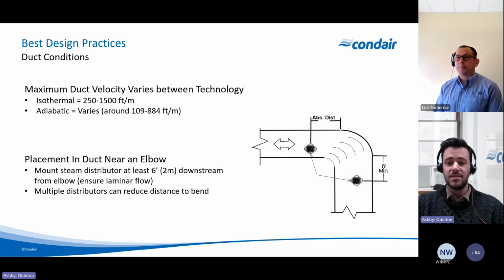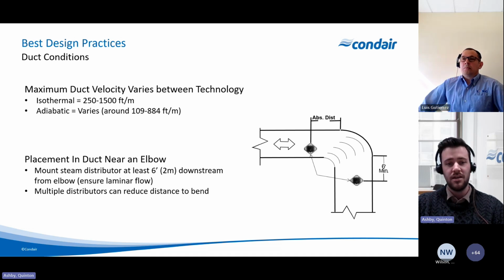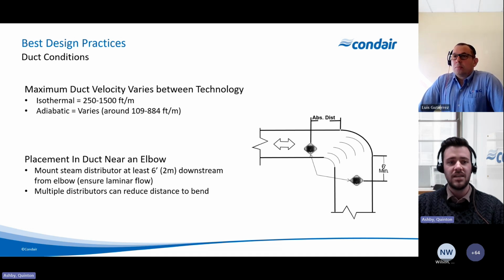Kind of going forward on that same path, there are things to consider in terms of velocity. Maximum duct velocities do vary between technologies. For isothermal, we typically say it's around 250 to 1500 feet per minute.